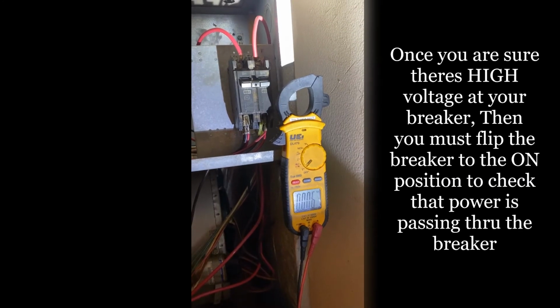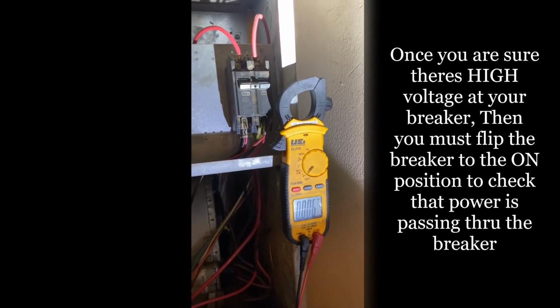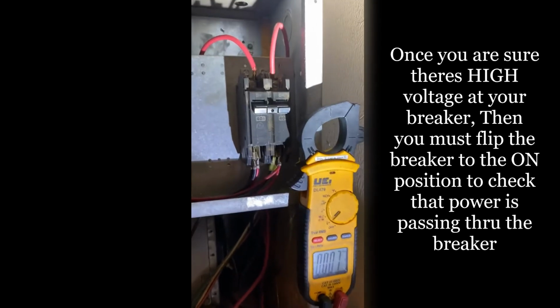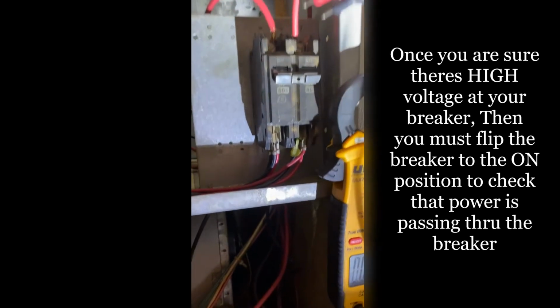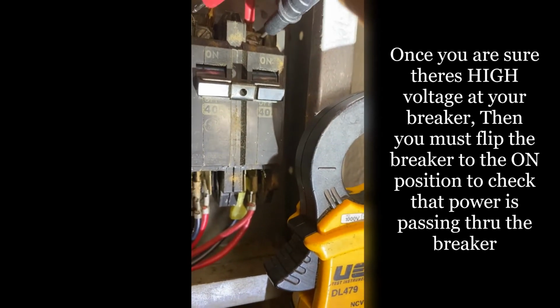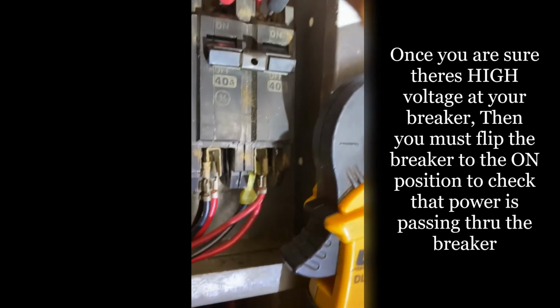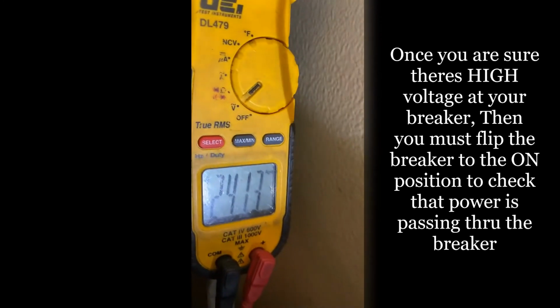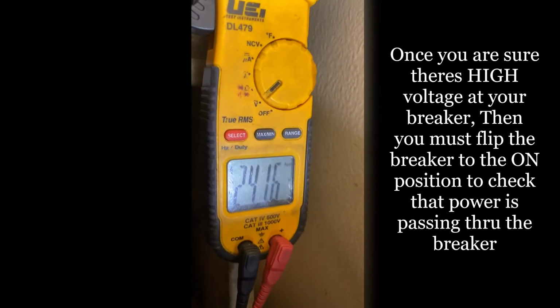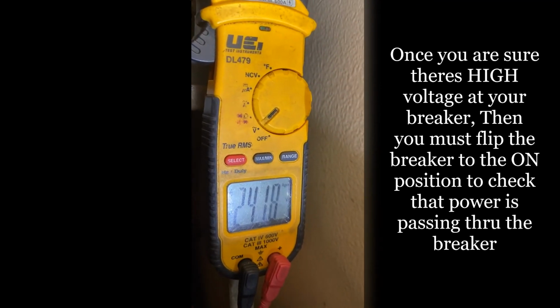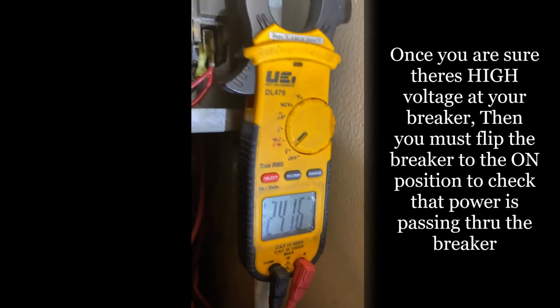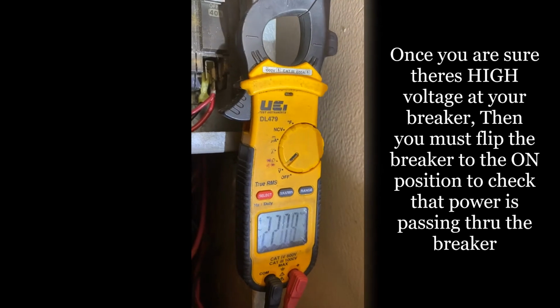All right, so we're gonna put our meter on voltage. We're gonna come to the incoming high voltage. And we're gonna check between the 2 terminals on top or on the bottom, wherever the power's coming in. And you see here I have 240. All right, you can have 208, 240. That's the average voltage.